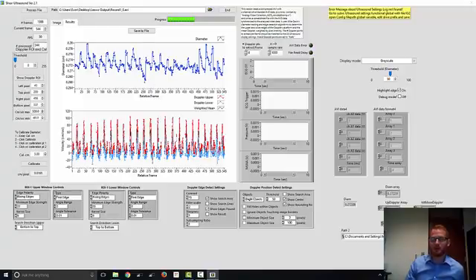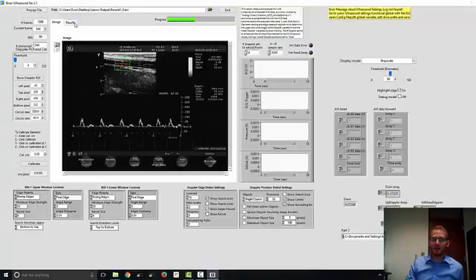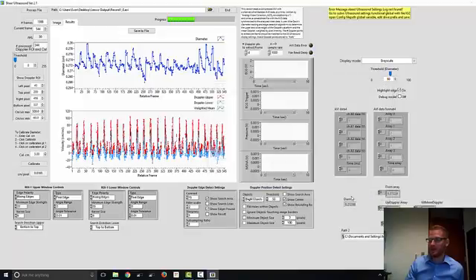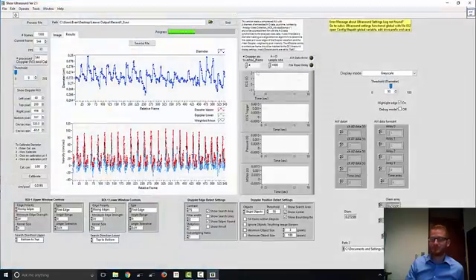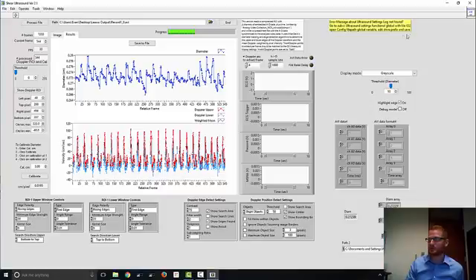Once you're all done, let's say you're watching this screen. Once it's all done, it's automatically going to pop to this results screen. And you have this button here that says save the file. You just click that. It would ask you where you want to save it, and you would just hit OK. And it saved the data that came out of that. And then at that point, you can hit this end button. If you want to do another ultrasound video through the software, you could at this point, just hit the white arrow and start again. Or you can just close out of the program, which is what we're going to do here.